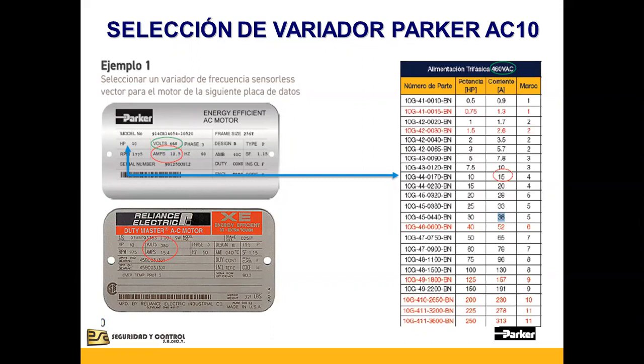Para la selección del AC10, solamente necesitamos saber tres datos importantes de la placa del motor: el voltaje, el consumo o la corriente en amperes del motor, y la potencia normalmente dada en HP. En las tablas de Parker, en la página de Seguridad y Control o en la página de Parker, pueden tener acceso a los catálogos o solicitarlos directamente.